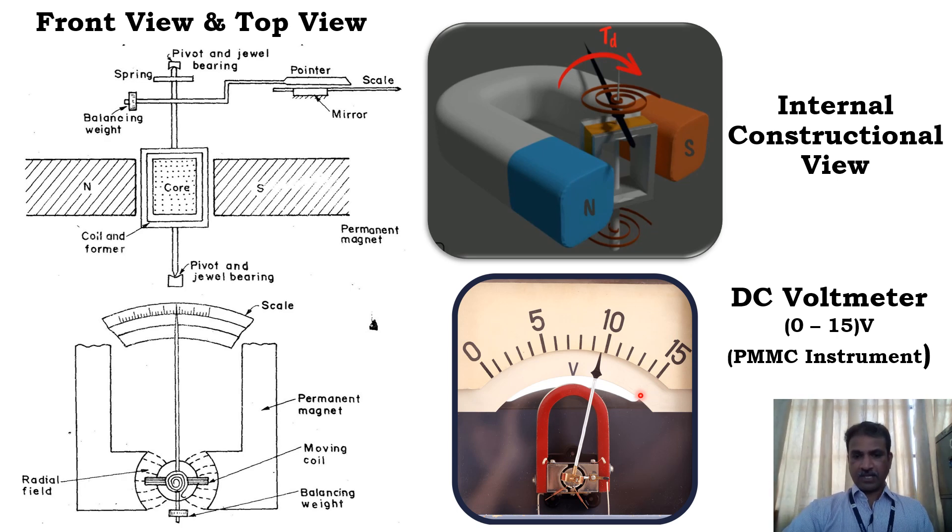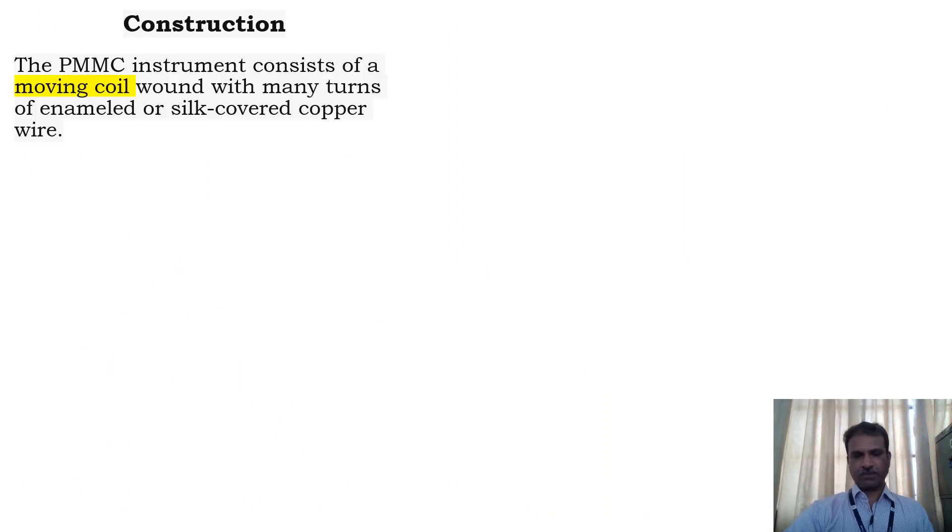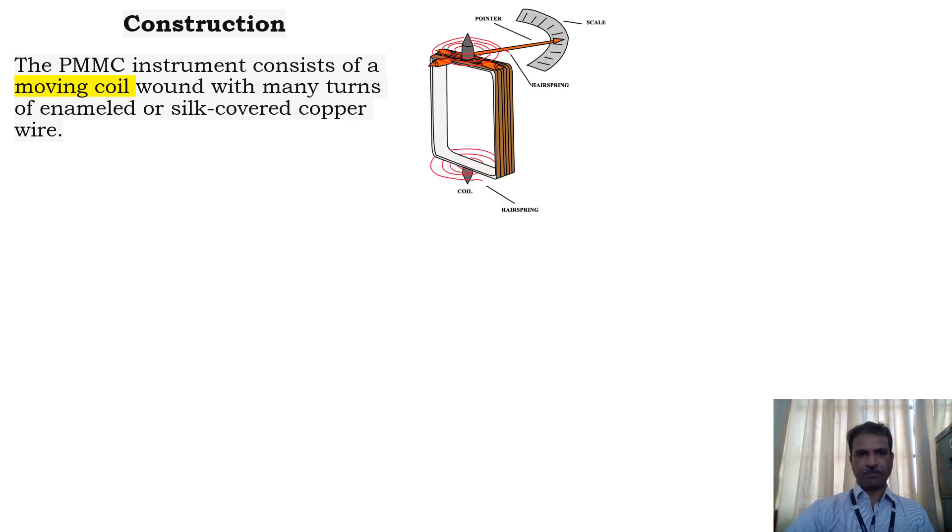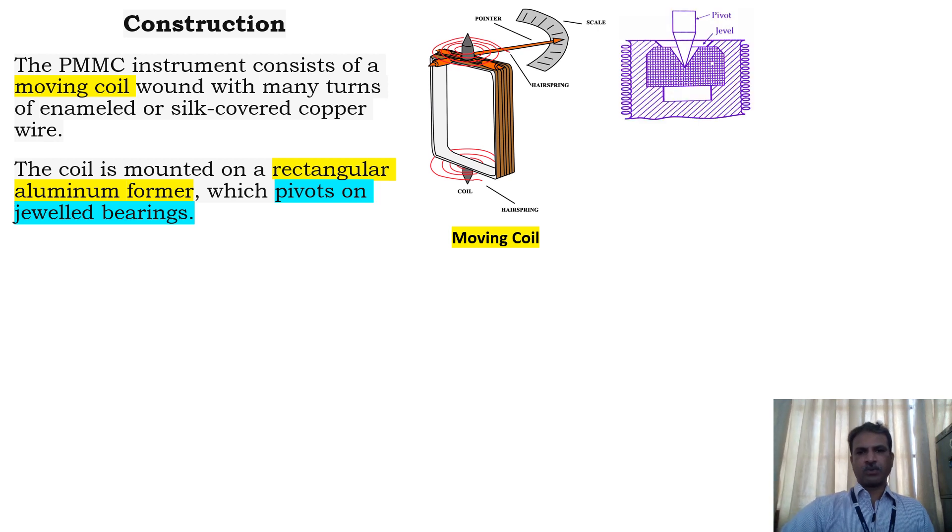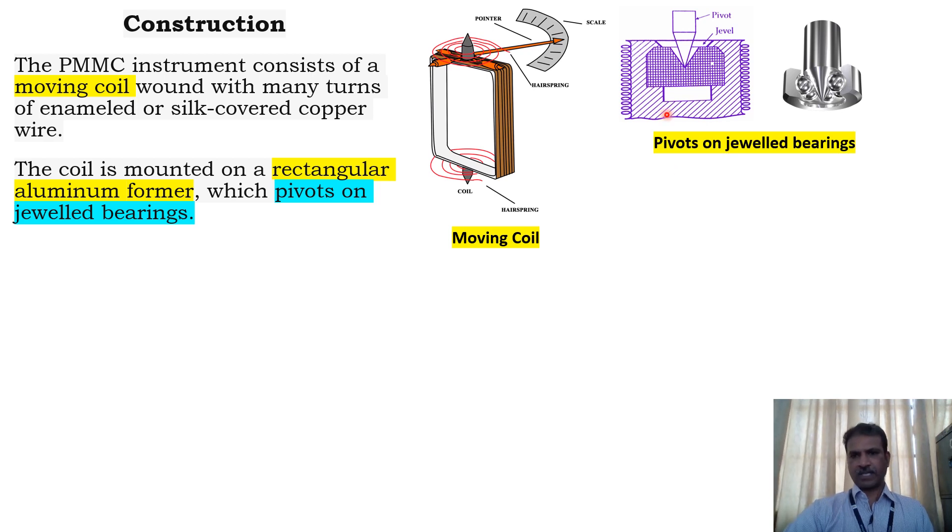Let's see the construction of the PMMC instrument. The PMMC instrument consists of a moving coil wound with many turns of enameled or silk-covered copper wire. The coil is mounted on a rectangular aluminum former which pivots on jeweled bearings. You can see it on the top right corner here.